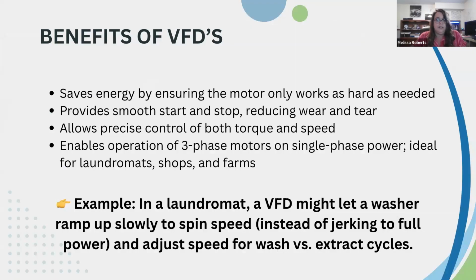Some benefits of VFDs: saving energy by ensuring the motor only works as hard as needed to perform its function, providing a smooth start and stop which reduces wear and tear on your motors, allowing precise control of both torque and speed, and enabling operation of three-phase motors on single-phase power, which is perfect for laundromats. So in the laundromat, the VFD lets the washer ramp up slowly to speed instead of jerking to full power, and adjusts for wash versus extract cycles, which run at different RPMs.